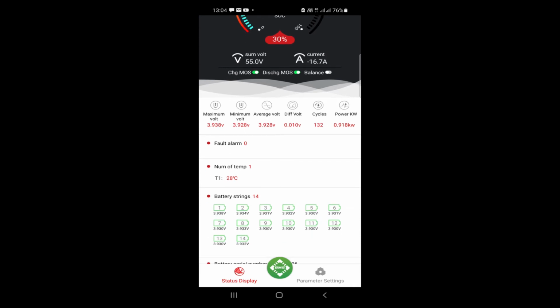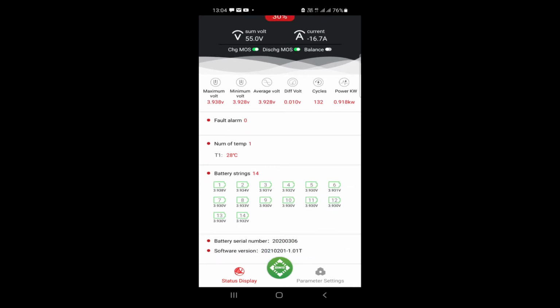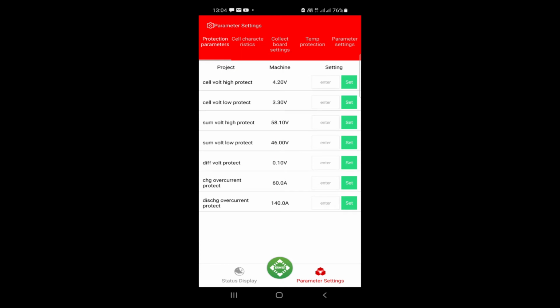Now we will check the parameters and correct them. Click on the parameters and you will get to this screen. Cell voltage high protect should be 4.2 volt for lithium ion NMC batteries. Cell voltage low protect should be 3.3 volt. Sum voltage high protect, that means for 14S, the sum of the voltage should be maximum 58.1 volt. Sum of low protect voltage should be set as 46 volt. Then difference voltage protection should be 0.1 volt.